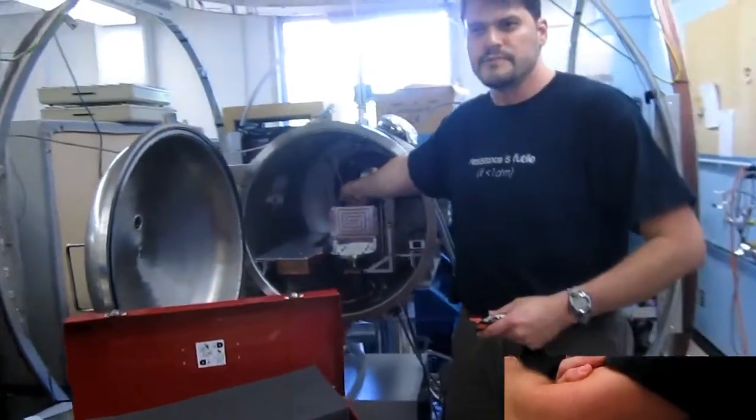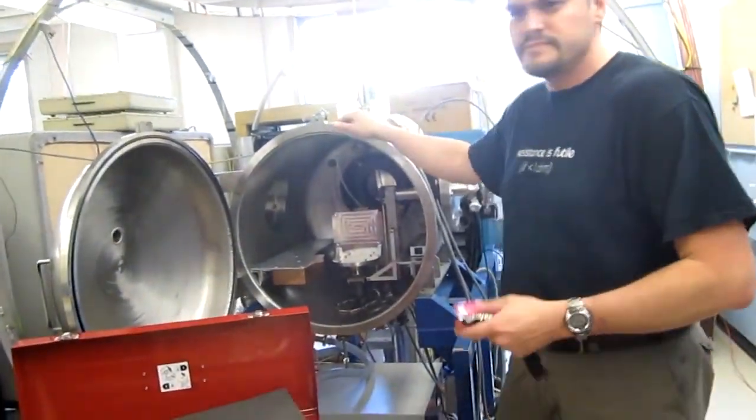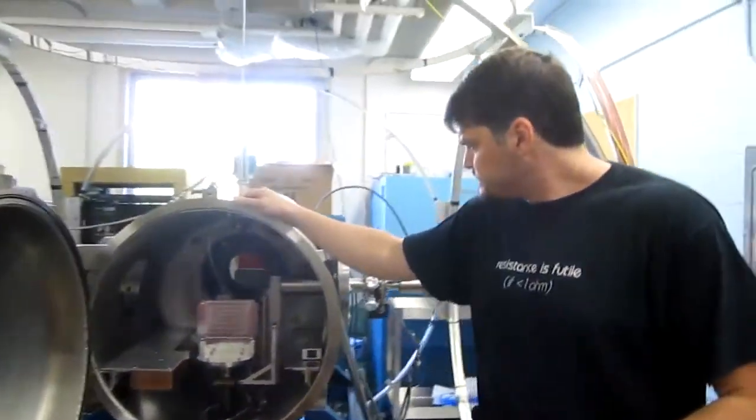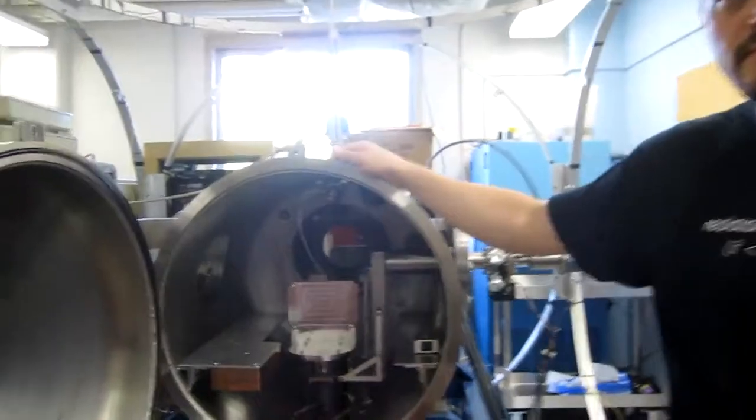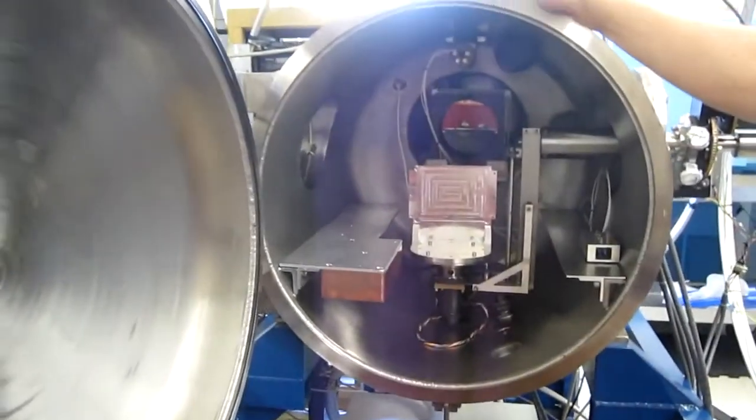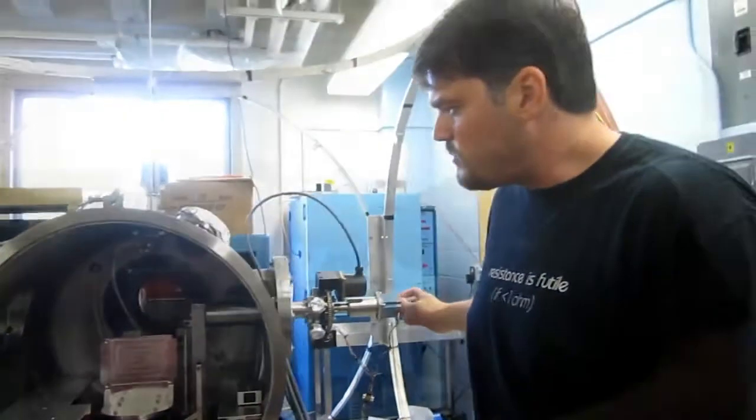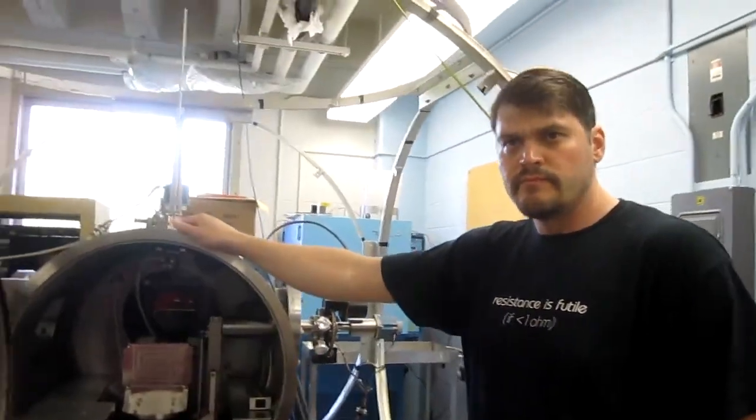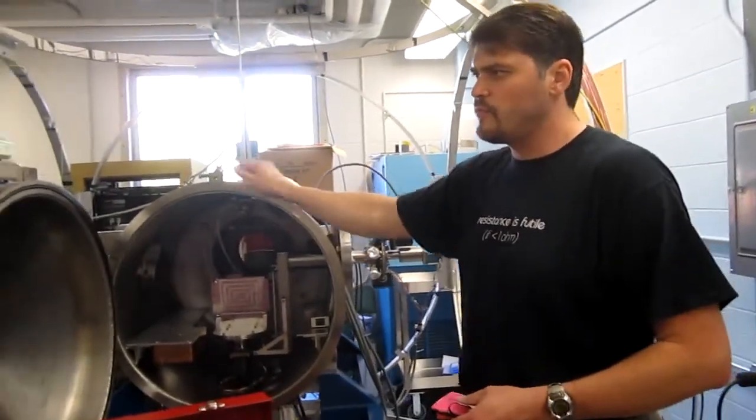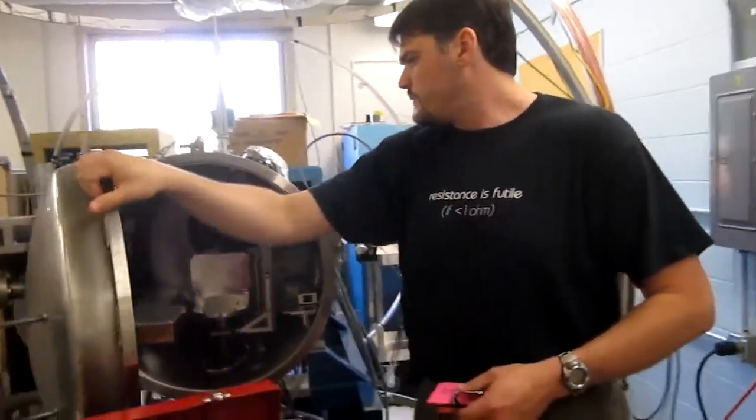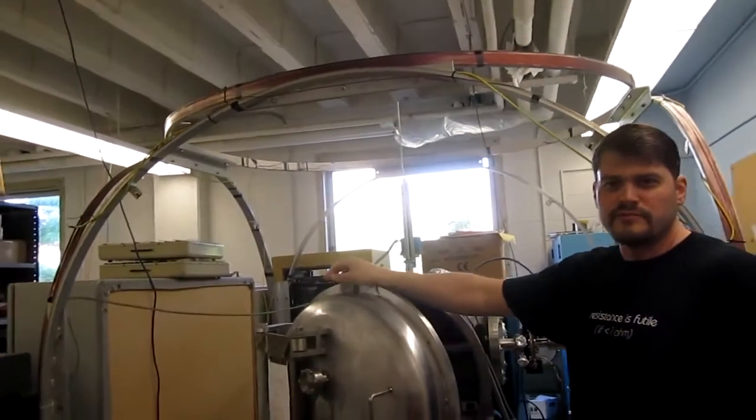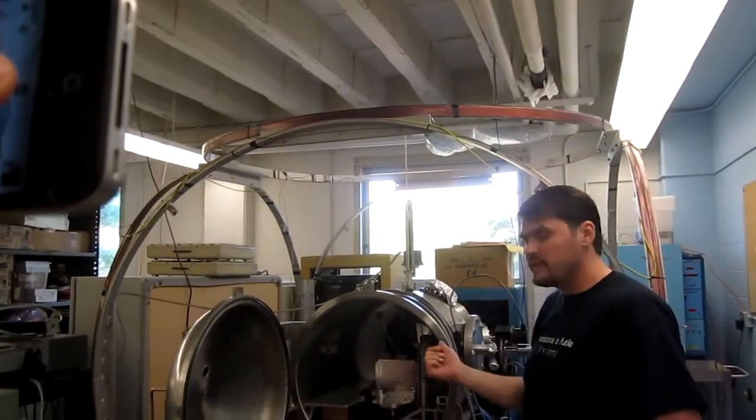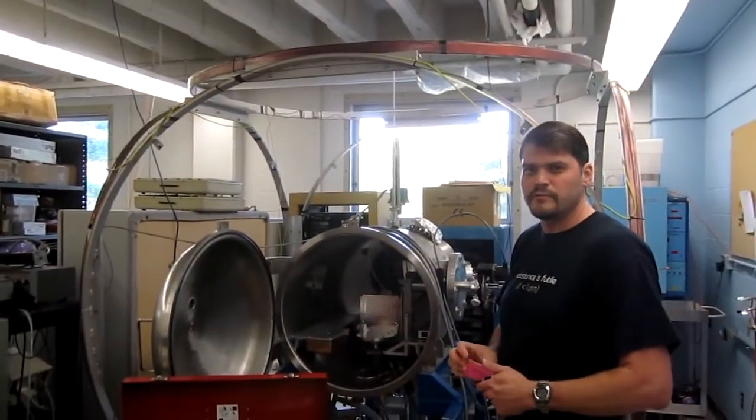The electron source will sweep through various energies of the electron to calibrate the detector. So you test all the detectors before you put them on the rockets. We test them in here before we deliver them because we can't test them in atmosphere because of the high voltage. So we throw them in here before we deliver them to the rocket.